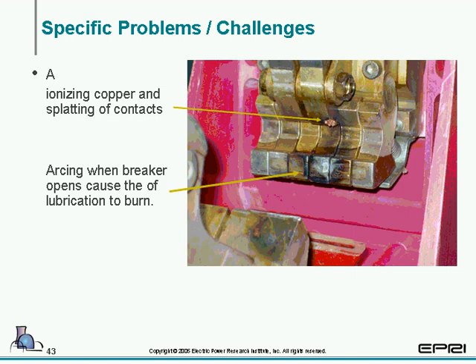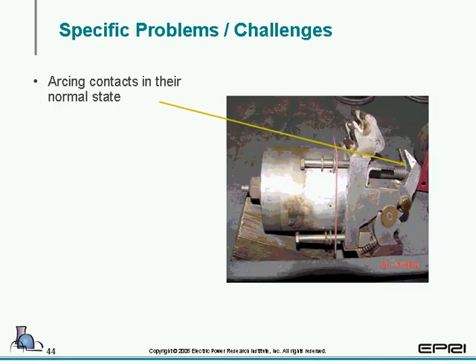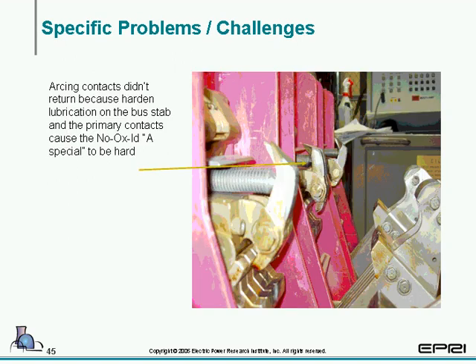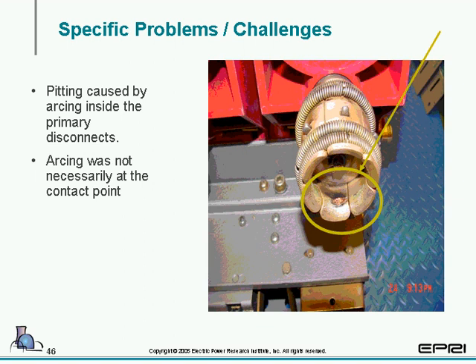And a close-up. You can see, in the very top one, we had ionizing or splatter. And again, where we had arcing with the breaker opening causing a burn. Now normally, in the normal state, we would see that the arcing contacts will reset themselves. On this particular breaker, you can see the middle set of arcing contacts did not reset, or actually push back, and they had locked themselves in that position, caused by the hardened lubrication drying out.